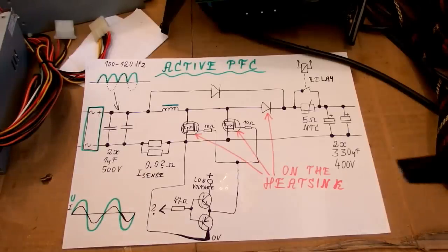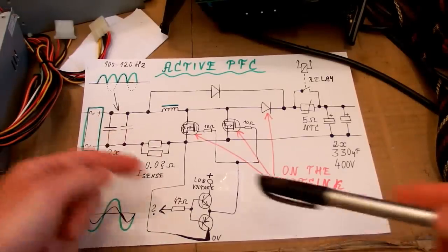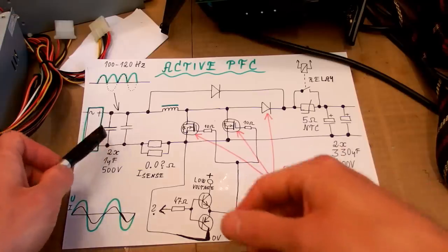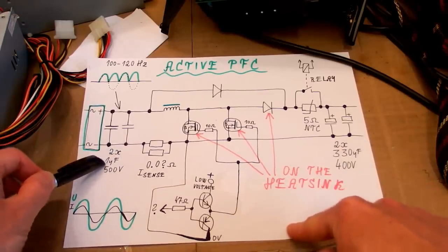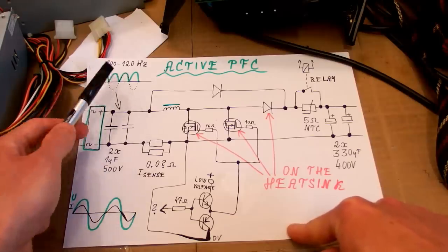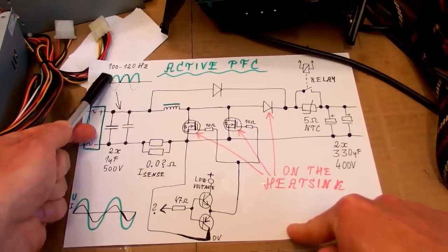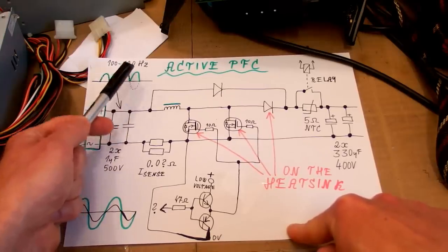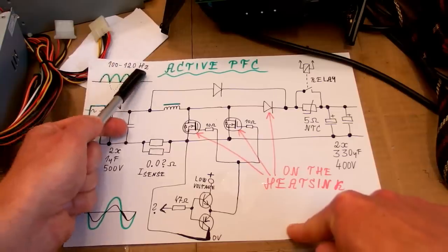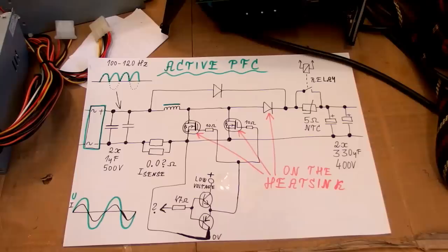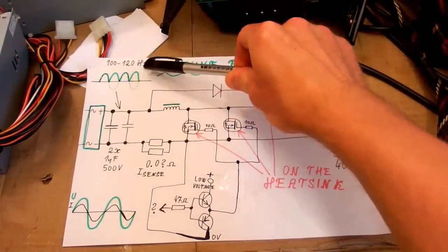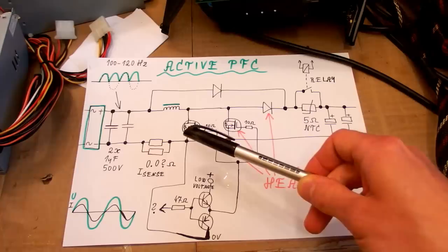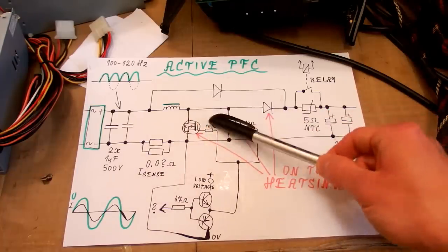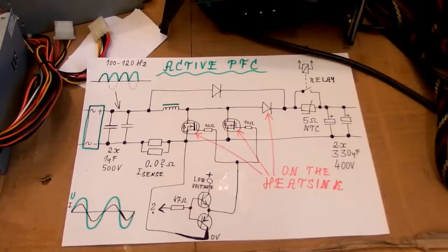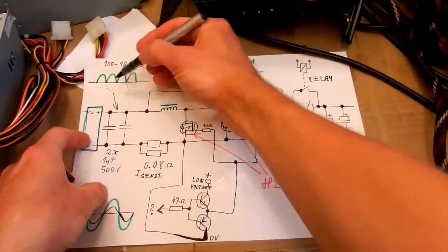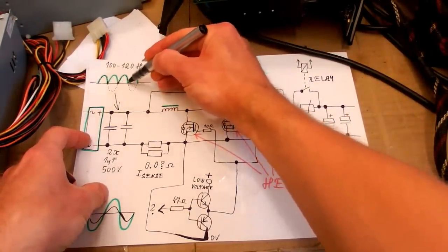It's basically a boost regulator, but with very low capacitance at the input. After the bridge rectifier there are some capacitors, but with very low capacity, so they don't smooth the rectified sine wave of the mains. There's basically a full ripple of the voltage at 100 or 120 Hz, double the mains frequency — these capacitors just filter high frequency interference from the switching regulator, so the voltage at those capacitors isn't smooth and basically touches zero.